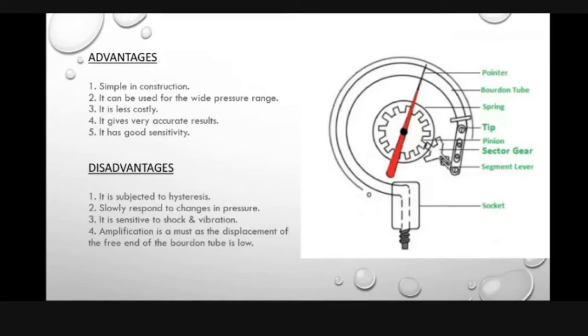Moving to the cons, that is, the disadvantages of the Bourdon tube. It is subject to hysteresis. It is proportional to the pressure, up to the maximum amount of pressure applied. Second, it responds slowly to changes in pressure. Third, while taking the reading, we feel the vibration due to the pressure. Fourth, amplification: the displacement of the free end of the Bourdon tube is low. Next slide.